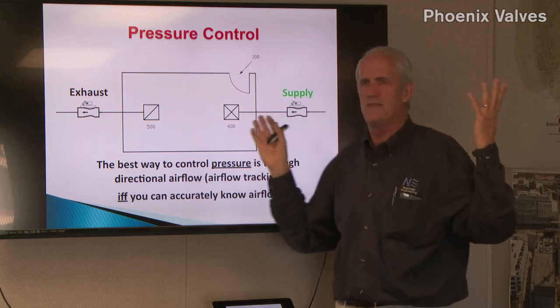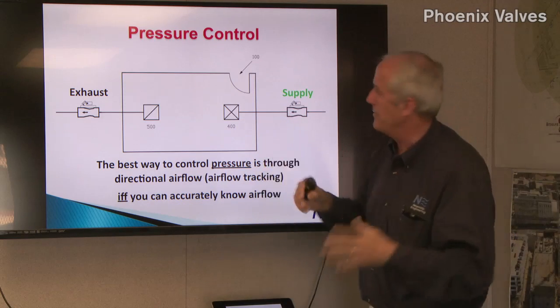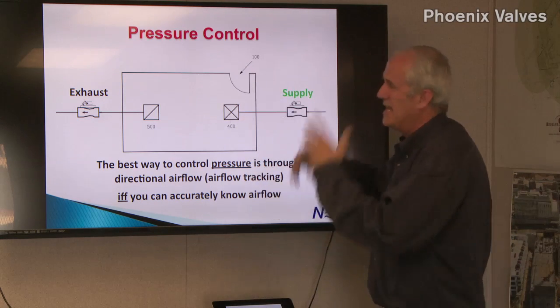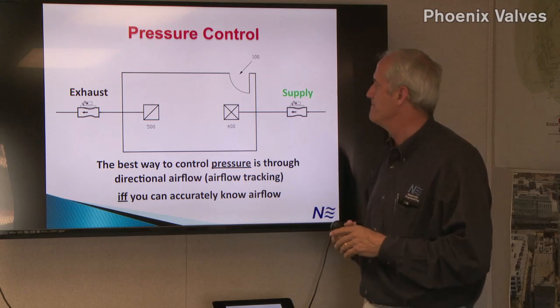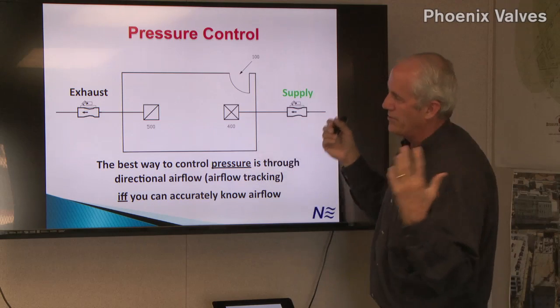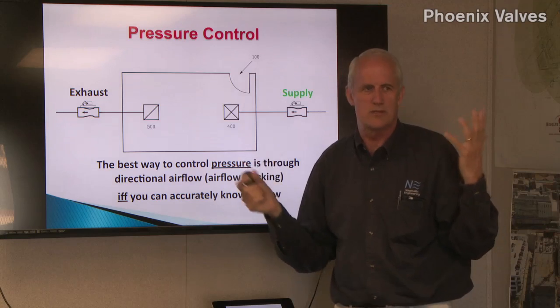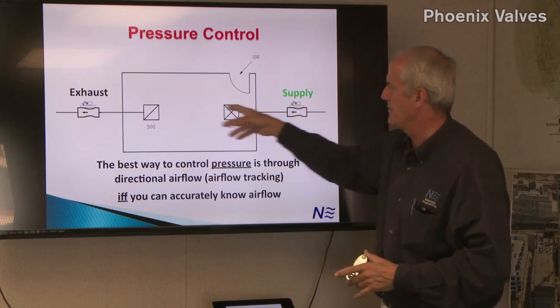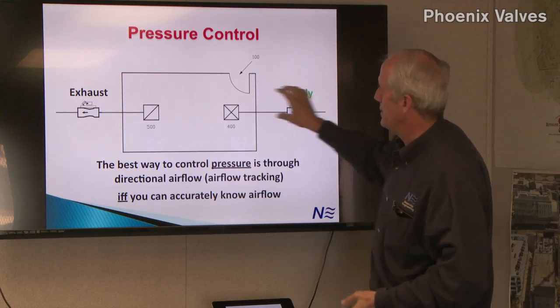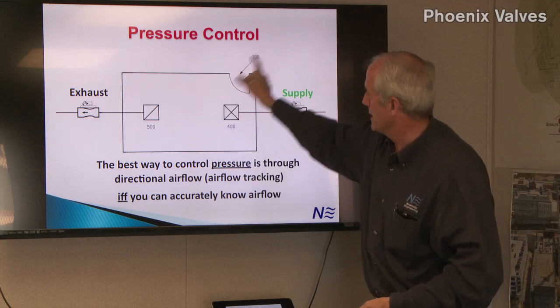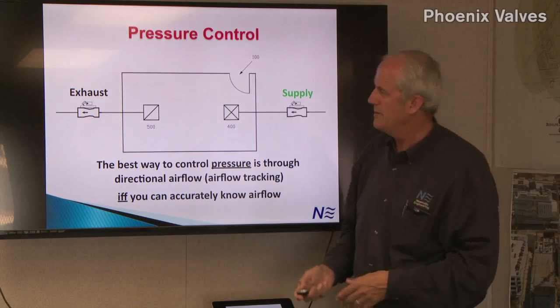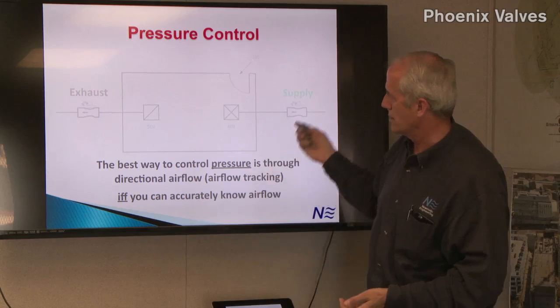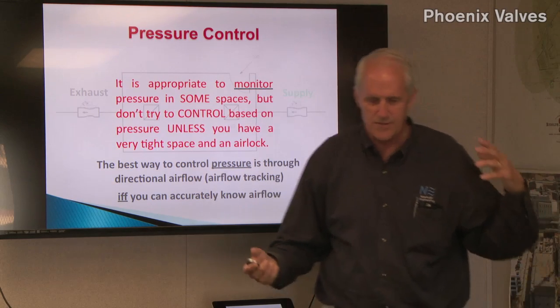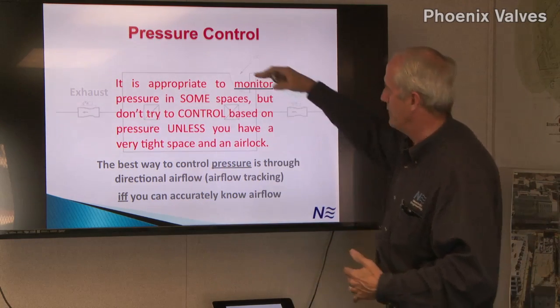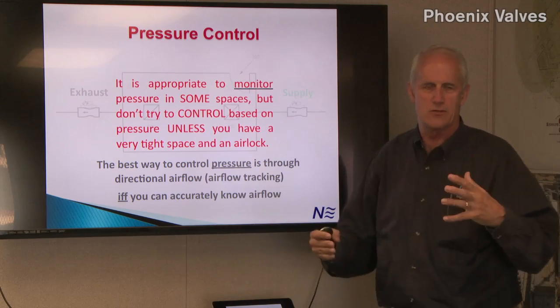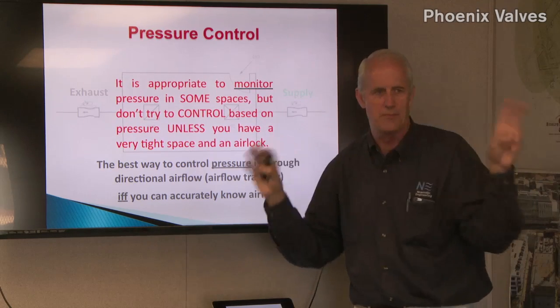When you open it, it's going to fall off the table. You're not going to have any measurable amount. So if you try to control based on that pressure, it goes crazy every time the door is open. Or you lock it out when the door is open, then they prop the door and you really don't know what's going on. So really the best way to do it is to accurately measure the supply and exhaust, know the difference, and make sure that the delta comes in through the door. Direct pressure really only works if you have an airlock, some kind of architectural barrier between the space you're trying to control and the neighboring space, so you never pop the bubble.